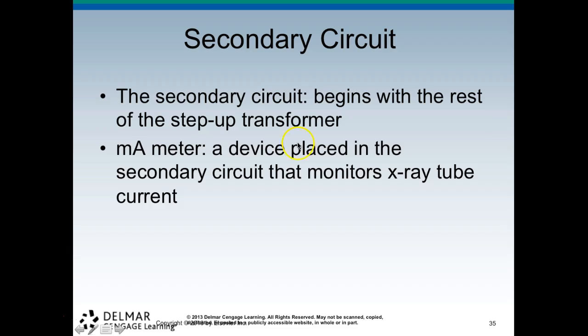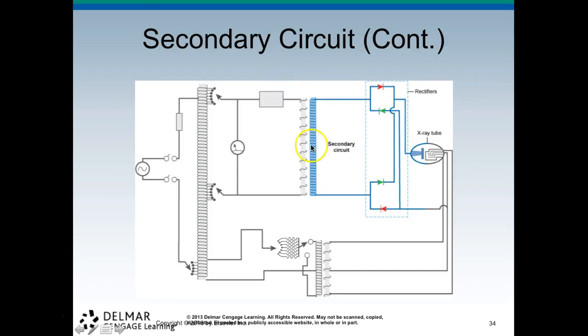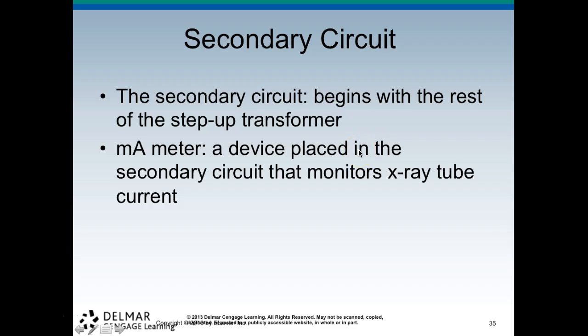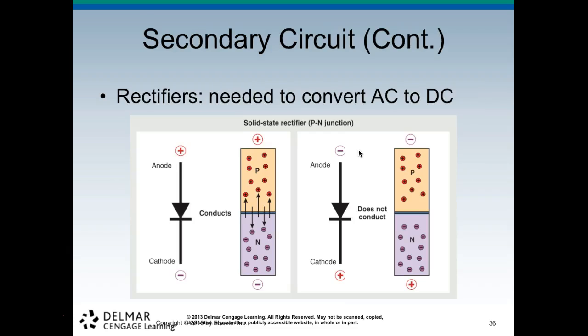All right, your secondary circuit, which is this side over here, begins with the rest of the step-up transformer. So it is the step-up side. It's not the primary side, but the secondary side. It has an mA meter, a device placed in the secondary circuit that monitors the X-ray tube current. And you can see there are rectifiers within that secondary circuit that convert the alternating current to direct current, which is really important.